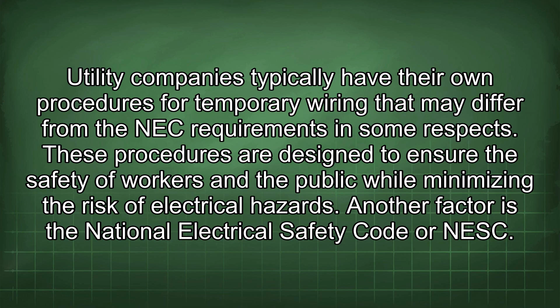Another factor is the National Electrical Safety Code, or NESC. The NESC is a separate standard that covers the construction, operation, and maintenance of electrical power and communication lines. The NESC is widely used by utility companies in the United States and is often referenced in state and local regulations. While the NEC focuses primarily on the wiring of buildings and structures, the NESC addresses the specific hazards associated with overhead and underground power lines, including clearances, grounding and mechanical strength.